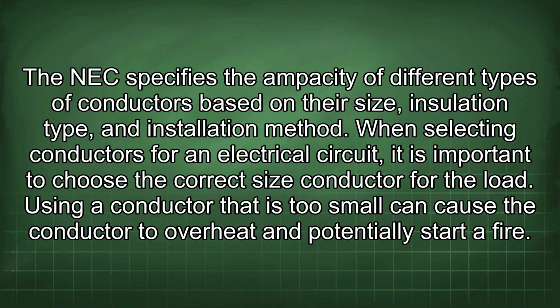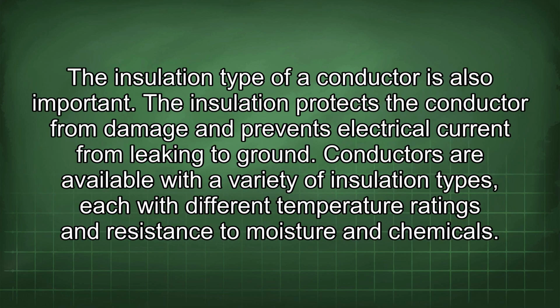When selecting conductors for an electrical circuit, it is important to choose the correct size conductor for the load. Using a conductor that is too small can cause the conductor to overheat and potentially start a fire. The insulation type of a conductor is also important. The insulation protects the conductor from damage and prevents electrical current from leaking to ground. Conductors are available with a variety of insulation types, each with different temperature ratings and resistance to moisture and chemicals.